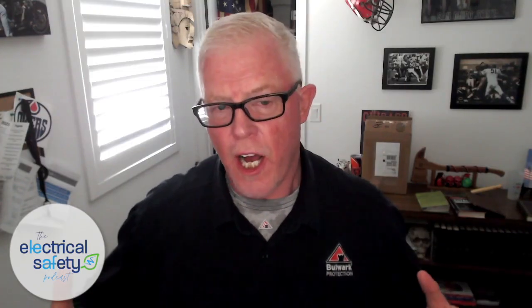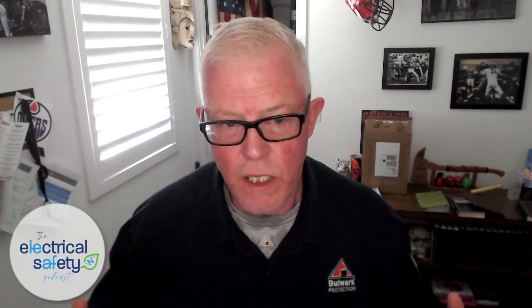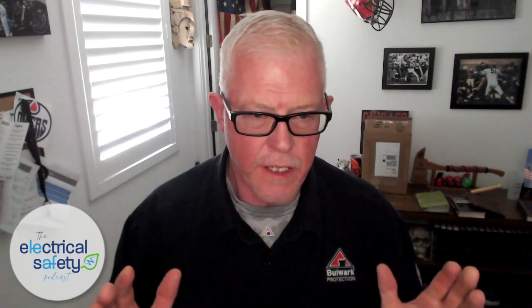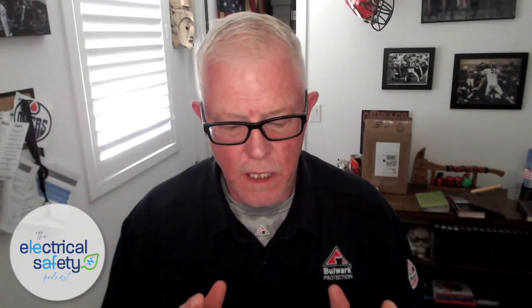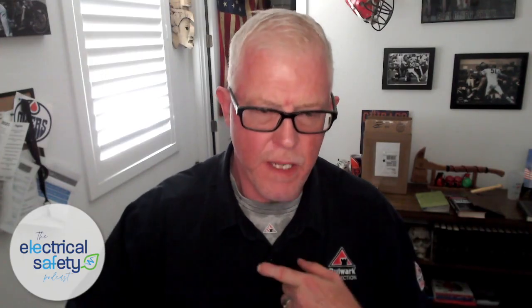Right. And you're not off, because remember, to get that arc rating on that piece of equipment, even if it's perfectly labeled within all the standards, that's still subject to two variables that the electrician typically can't control. One is distance. It's usually measured at 18 inches. So if my electrical worker has to get a little bit closer, he's going to have more incident energy exposure. How much? We don't know, because we don't give them 10 inches, 12 inches, 18 inches. We give them 18. So if I just lean in a little bit, I'm going to get more.